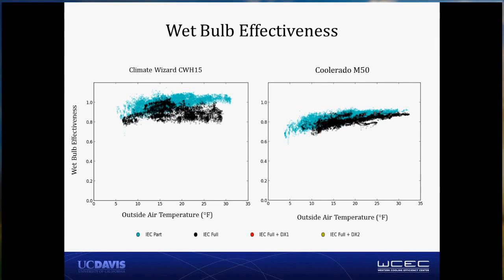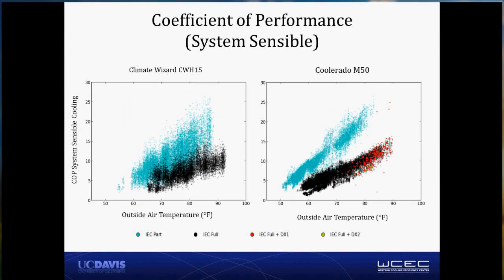It's important to realize that with this indirect evaporative heat exchanger strategy, you can achieve a higher wet bulb effectiveness by sacrificing some airflow and by using more fan power. So when we actually look at the coefficient of performance for these systems, they look much more similar. So again, I'm charting this time by outside air temperature. We're looking at the COP of the system. The marks in black show full speed operation, and the marks in blue show part speed operation.